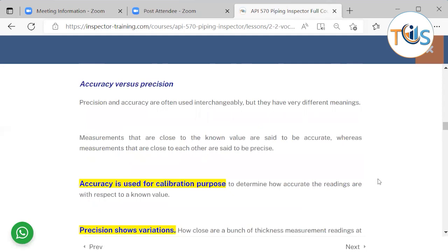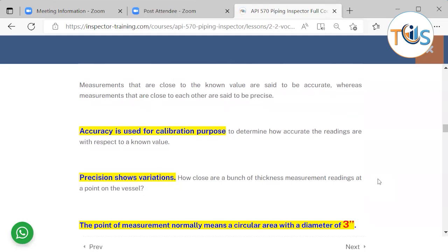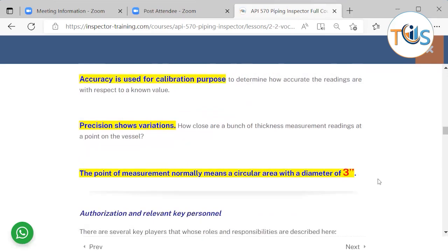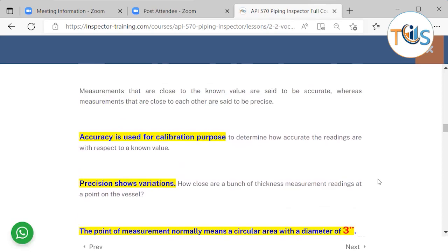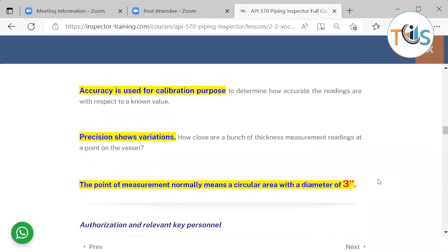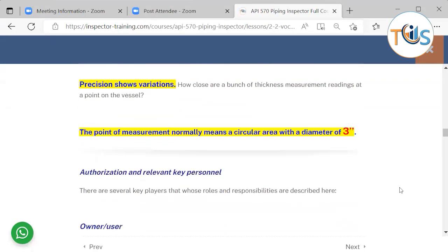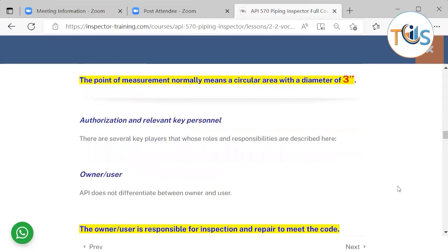Accuracy versus precision: they are often used interchangeably but have very different meanings. Accuracy refers to measurements that are close to a known or true value, and is used for calibration purposes. Precision is about variation — measurements that are close to each other. The point of measurement normally means a circular area with a maximum diameter of 3 inches, also called a condition monitoring location, testing point, or examination point.